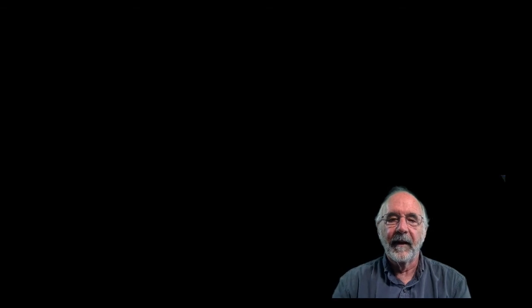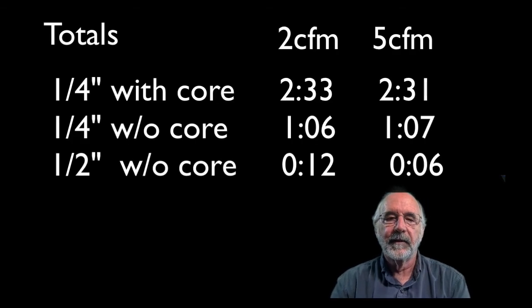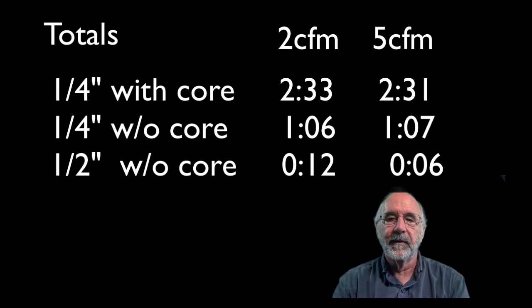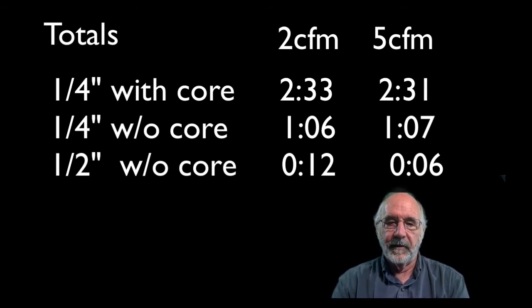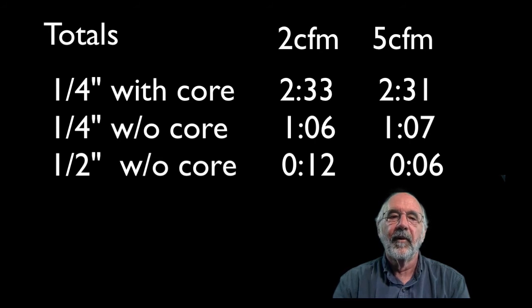So as a review here, here are the numbers. With the Schrader in place using a quarter inch hose, both pumps took two and a half minutes. With the Schrader removed using a quarter inch hose, both pumps took a little more than a minute.